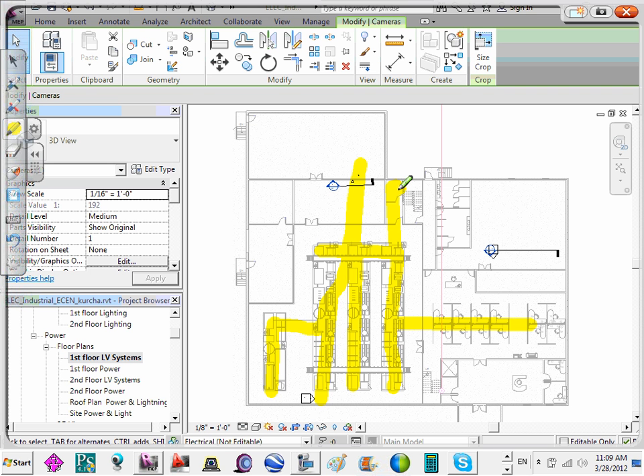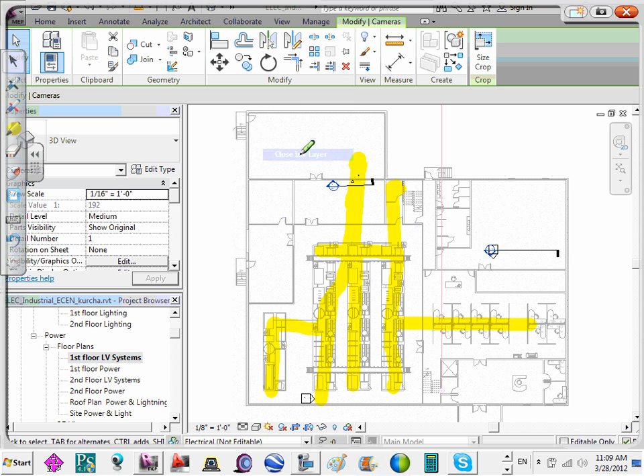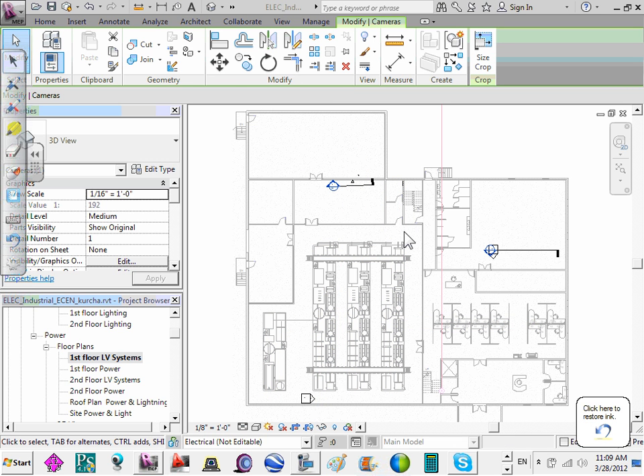One way cable trays are really great when you're talking about voice data is that you've got bundles of wire going through there, and trying to put that in conduit or run it up and support it is difficult. So cable trays come in handy. But one thing to know is that, like the fire alarm system, if you're running it in the cable tray, it has to be separated from 120 volt wire, and that's just a code requirement. It is NEC 760, if I remember correctly.